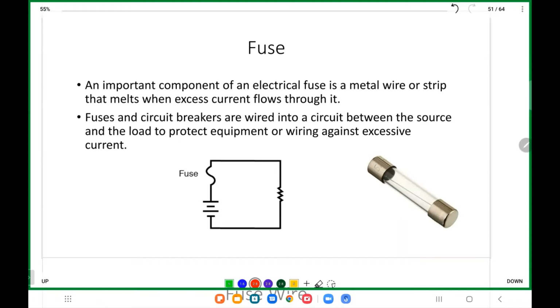Once this fuse is blown, you cannot replace it because the wire is broken, melted. That's the protection for overload current. You have this also inside your car. You'll find fuses with a nice plastic cover, red and blue, with two metal parts, but inside there's a wire, sometimes visible through a glass window. They come in different amp ratings, like 2 amp, 5 amp, 10 amp, 20 amp. A 5 amp fuse means if you exceed 5 amp, it will blow. That's for protection.